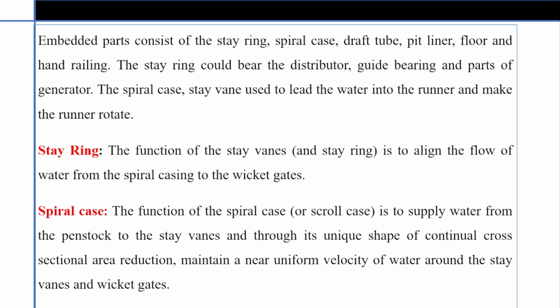Embedded parts consist of the stay ring, spiral case, draft tube, pit liner, floor, and railing. The stay ring could bear the distributor, guide bearing, and parts of the generator. The spiral case is used to lead the water into the runner and make the runner rotate. Stay ring. The function of the stay vanes and stay ring is to align the flow of water from the spiral casing to the wicket gates.